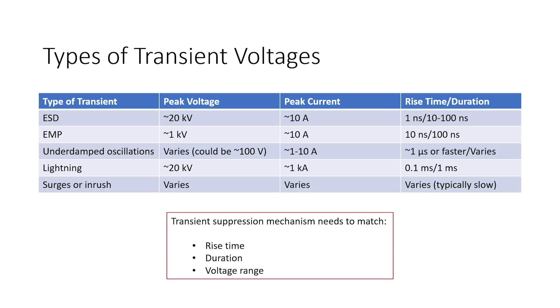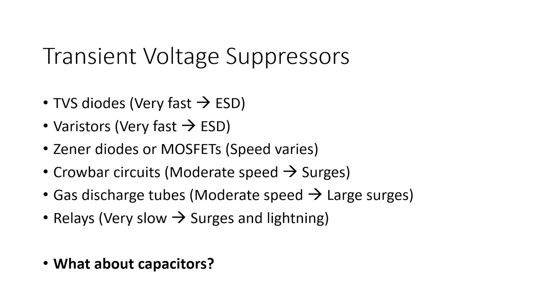So whatever mechanism that you use to suppress transient voltages, it needs to match or be able to respond to the rise time. That's the first criteria that we use to determine whether or not a particular component is going to be suitable for transient voltage suppression. The other is the duration, so how long can it withstand that transient voltage, and then what range of voltages can it withstand.